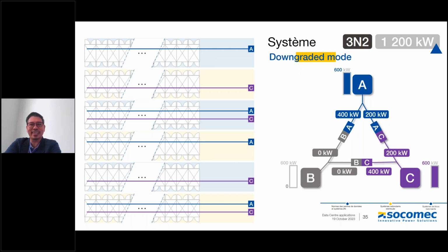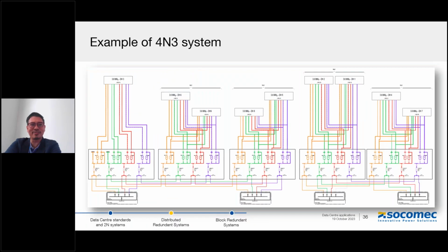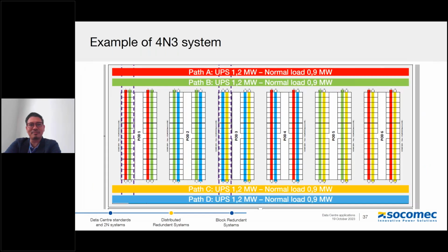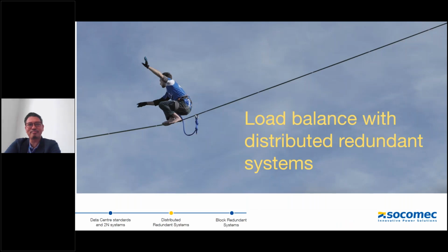And it becomes more complicated when we go with a 4N solution, 4N3, where you have multiple power trains. You can see here in the diagram, this is an example of a co-location data center. There are 4 power supply channels distributed in the data center hall or the IT room, powering multiple pods, multiple server pods in the solution. If we look closely, how can we maintain the reliability of the design? One key thing that plays into the picture is balancing.